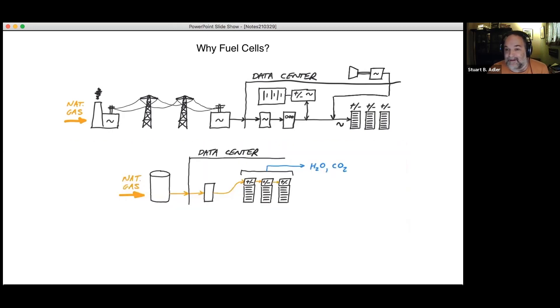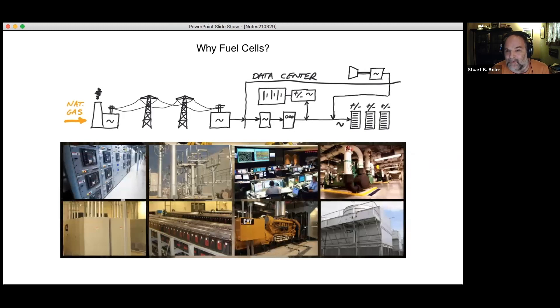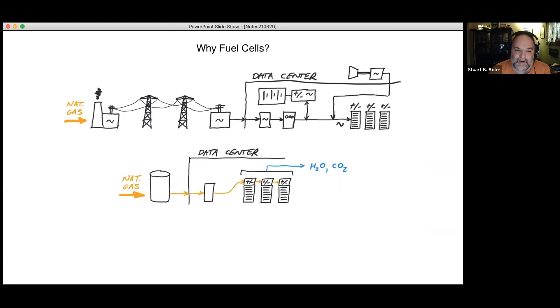And so that's why people are, that's another reason people are interested in fuel cells is because of the simplicity. So imagine taking that whole electrical infrastructure that we're currently kind of beholden to and replacing it with distributed power. And the idea is, you send in the same fuel, but it's stored in a tank. You've got nine days of storage if you need it for however long the outage is going to be. And then you feed it to fuel cells and the fuel cells are right in the data center. You take the electricity that you're making and you feed it directly into the rack that it's sitting on top of. And there's no AC rectification because there's no AC power. We're taking fuel. We're making DC electricity. We're feeding it directly into the computers and then the exhaust products come out of the data center.